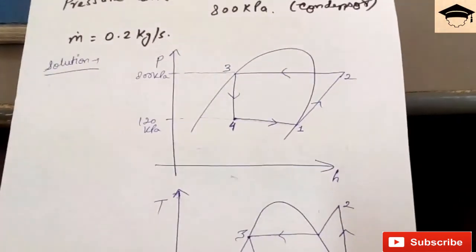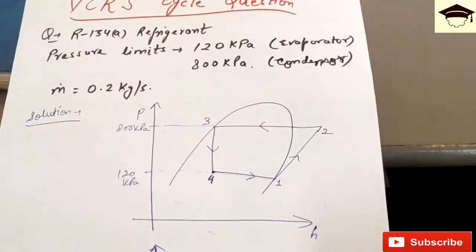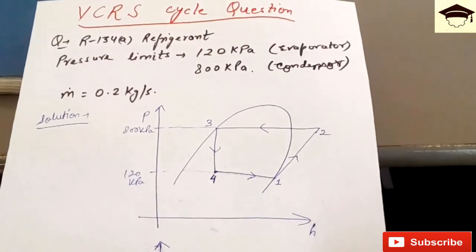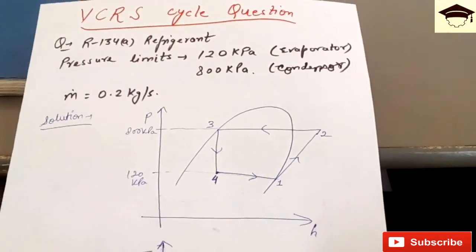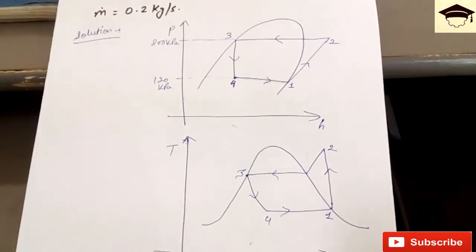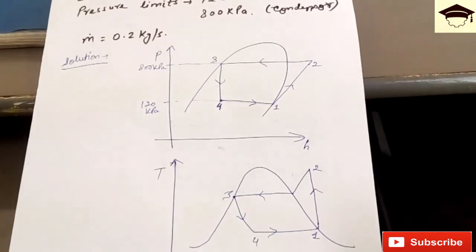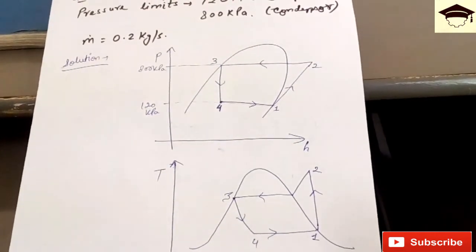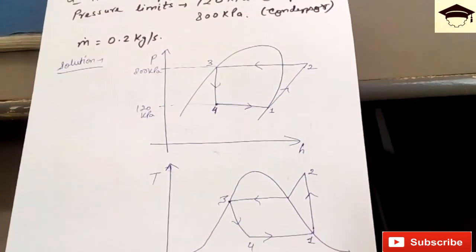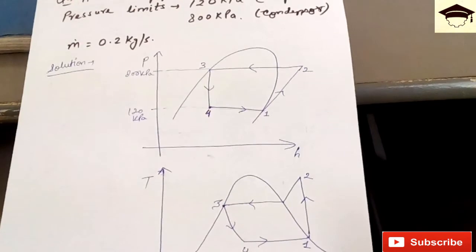Now the pH diagram corresponds to this and the TS diagram corresponds to this. Point 1 is the inlet of the compressor, 2 is the outlet of the compressor, 3 is the outlet of the condenser, 4 is the outlet of the expansion valve. Refrigeration effect is h1 minus h4, and the power or work input needed in the compressor is h2 minus h1. Now we have to find the values of h at the corresponding points 1, 2, 3, and 4. Note that h3 is equal to h4.